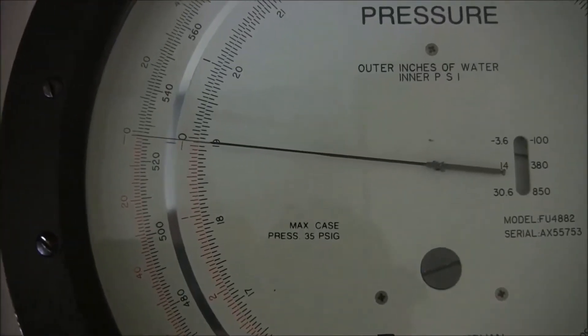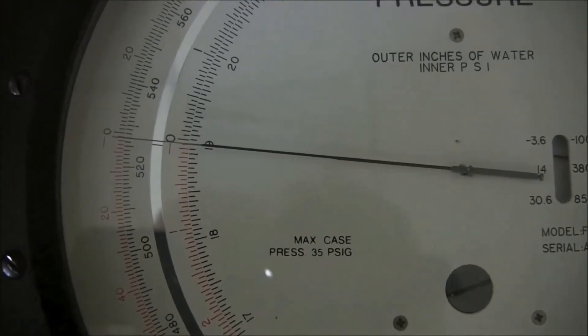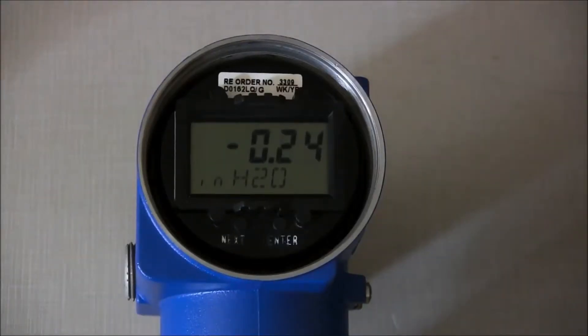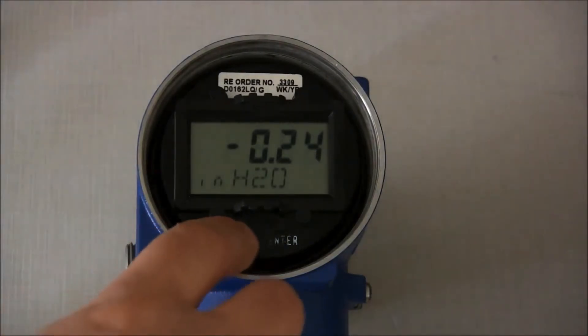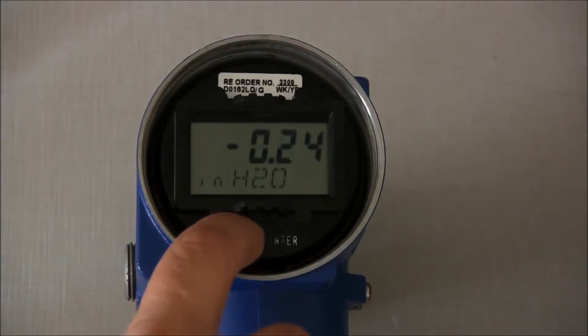With the pressure calibrator set to our lower range value pressure of 0, we would press the Next button three times and the display should indicate calibrate.